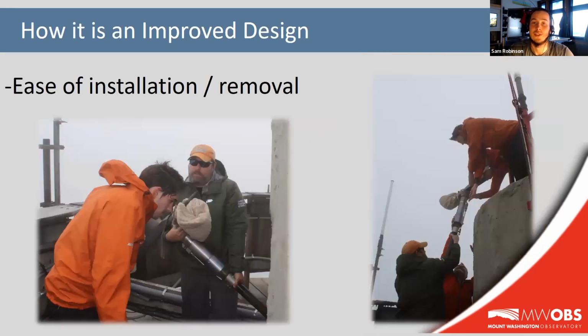So as you might be able to guess, this feature also eliminated that long unbendable section of copper tubing and simply replaced it with electrical wires. These wires have connections down in the cold room that simply have to be unplugged if that instrument needs to come down, making for a much easier removal and installation process when need be. This instrument does weigh quite a bit, so it still requires a few sets of hands, but the whole process usually is much quicker and smoother, and it definitely requires less precision and worrying about damaging any parts of the system. I do know from experience that this thing is pretty burly, pretty heavy, but it's a worthwhile trade-off for a robust design that accomplishes those goals we were trying to achieve.